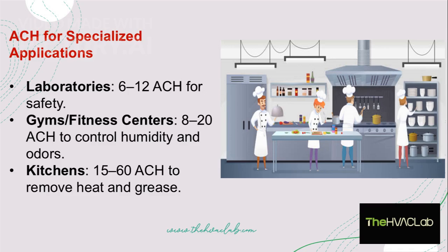Laboratories require 6 to 12 ACH for safety. Gyms and fitness centers need 8 to 20 ACH to control humidity and odors, and kitchens need 15 to 60 ACH to remove heat and grease.